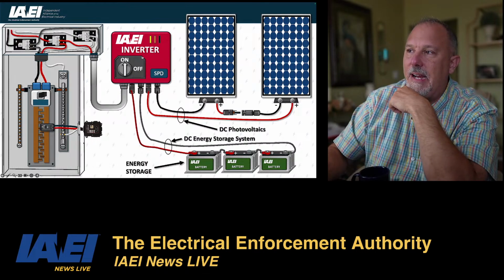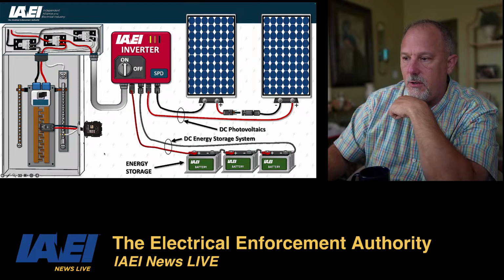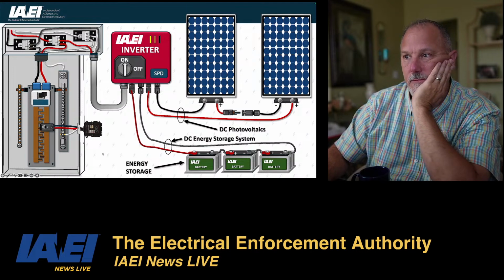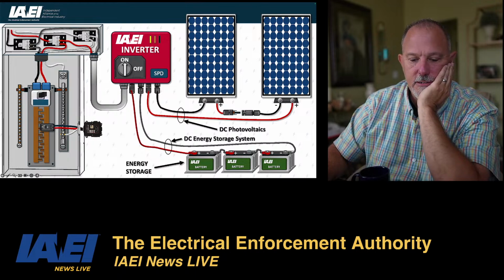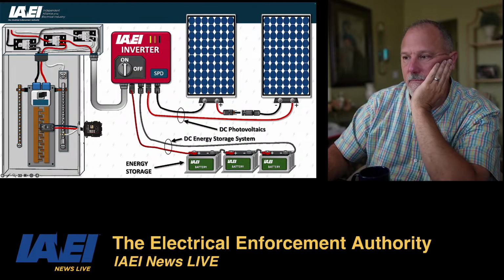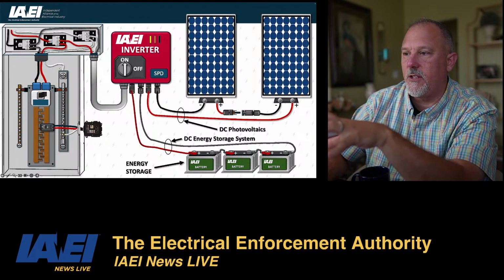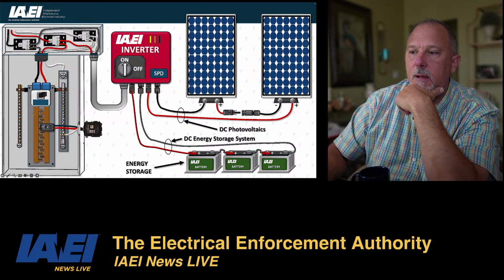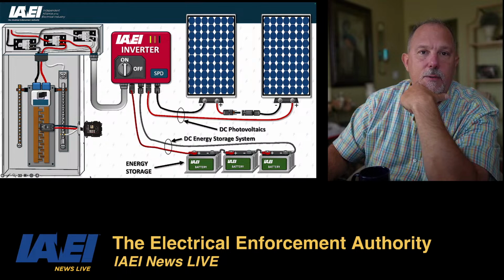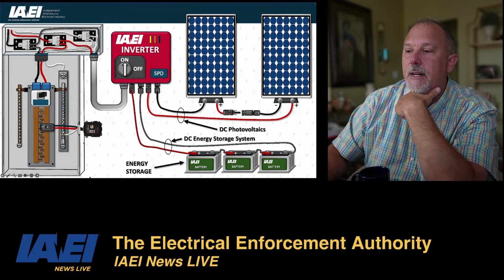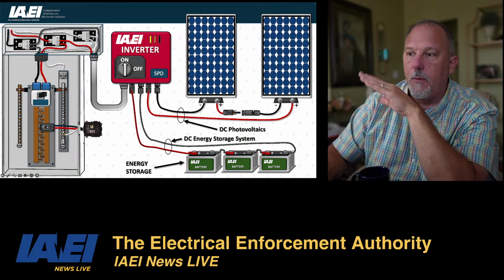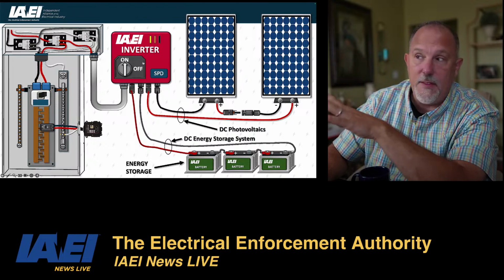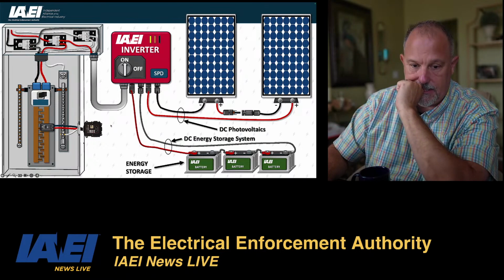Now that all has to be done, and I don't show my ground rod. Somehow I lost my ground rod. It's in here somewhere. It's in a different picture. I think in copying and bringing this over, I forgot my ground rod. But I have to have my ground rod, my grounding electrode conductor, connected to my grounding electrode for both this service panel board and the inverter. So I'm going to have to add that.